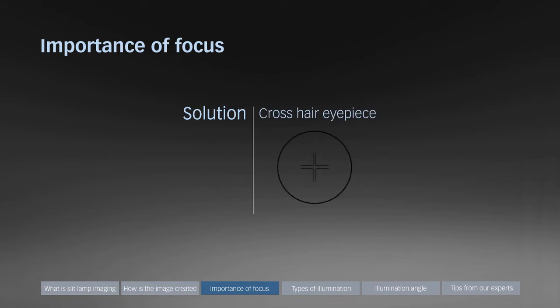To help overcome this problem, Haag-Streit has developed a special imaging crosshair eyepiece. A crosshair reticule indicates the correct adjustment of the eyepieces, thus a perfect focus for the camera is guaranteed.